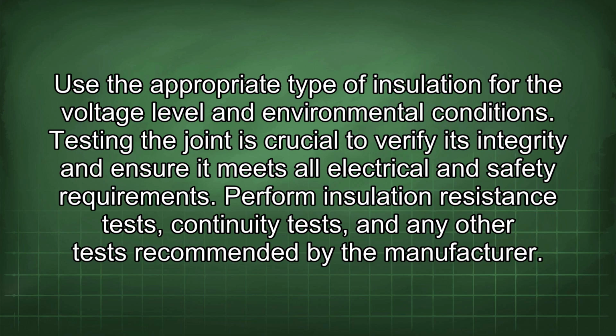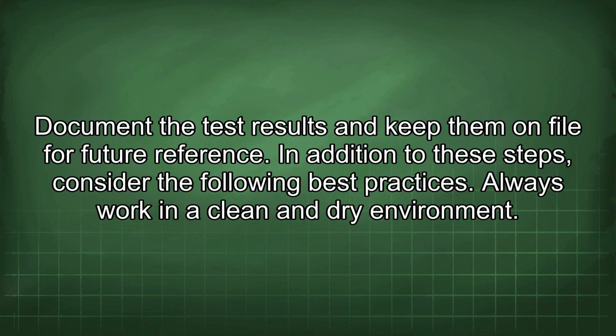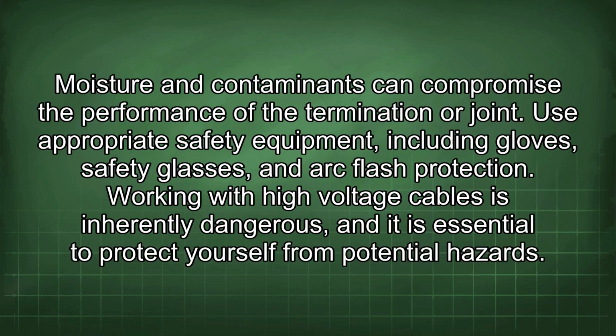Testing the joint is crucial to verify its integrity and ensure it meets all electrical and safety requirements. Perform insulation resistance tests, continuity tests, and any other tests recommended by the manufacturer. Document the test results and keep them on file for future reference. In addition to these steps, consider the following best practices. Always work in a clean and dry environment. Moisture and contaminants can compromise the performance of the termination or joint.